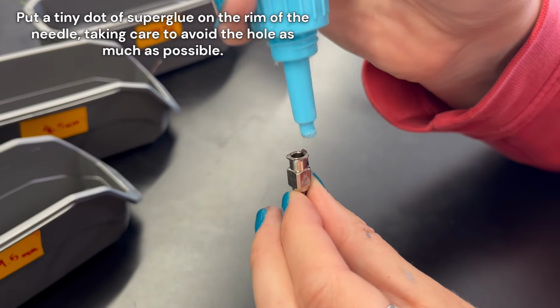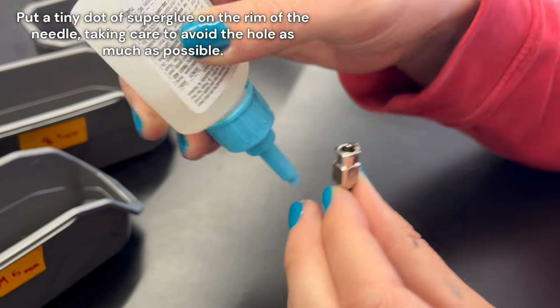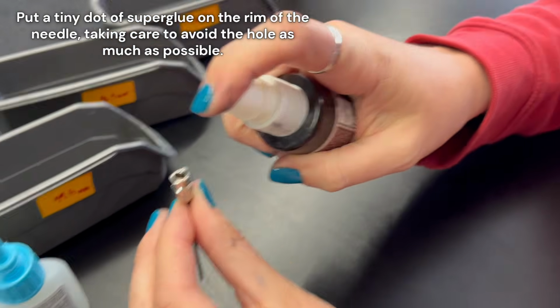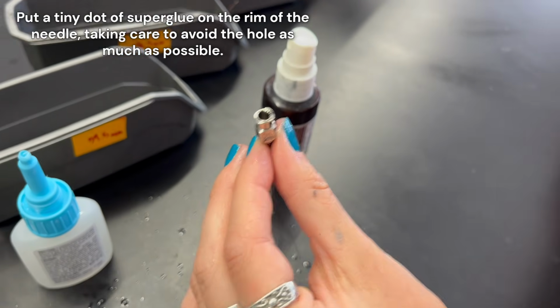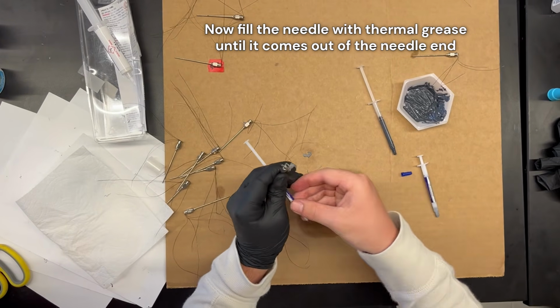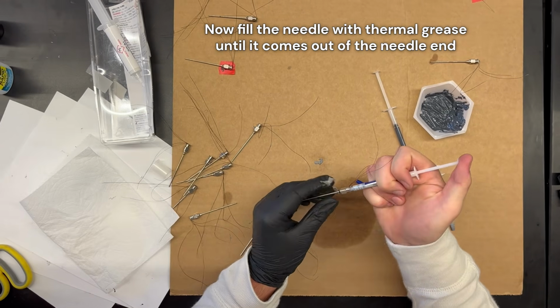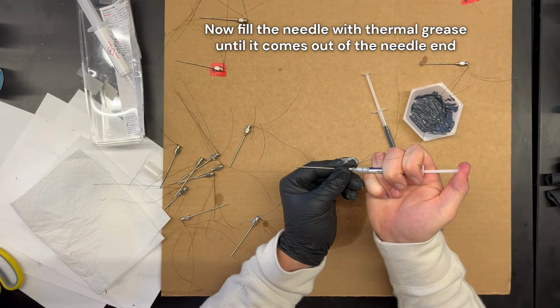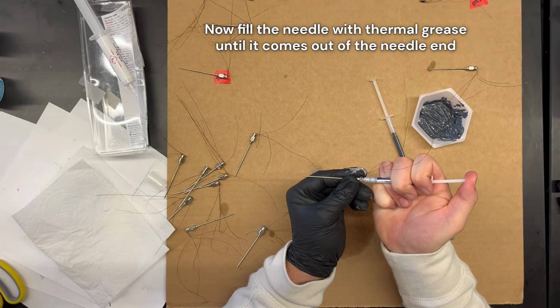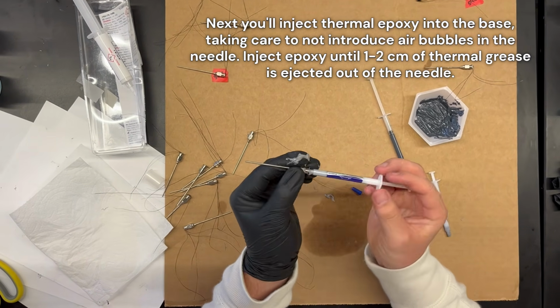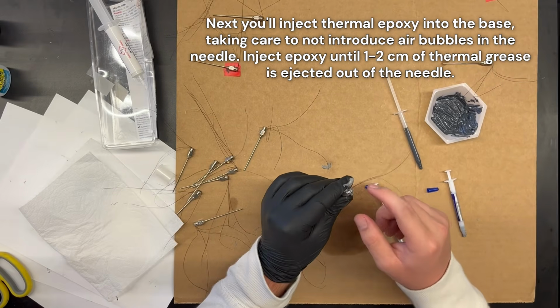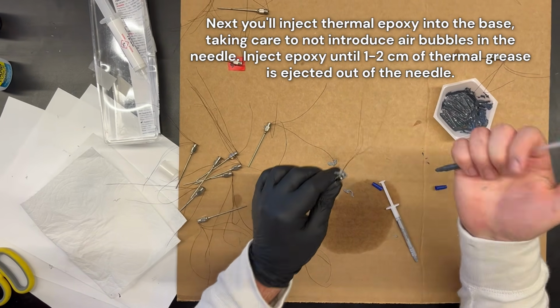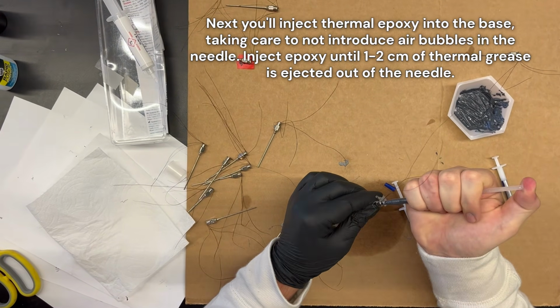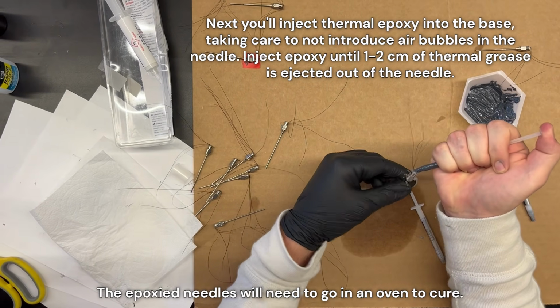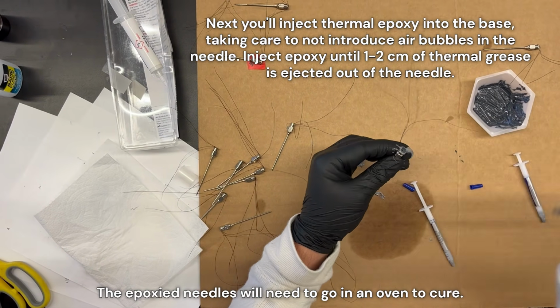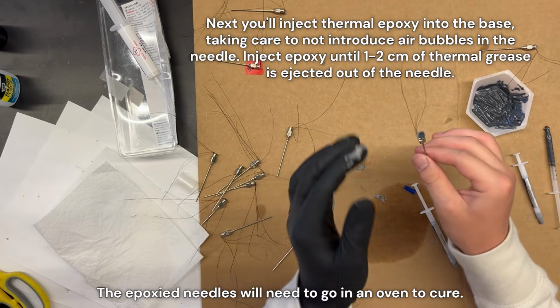Use a drop of superglue to hold them in place, and if you have it, you can use accelerant to cure the superglue instantly. You can either fill the needle completely with thermal epoxy, or use thermal grease to make it easier, as we do here. Fill the needle with grease until it comes out of the end, and then mix a batch of the thermal epoxy and fill a syringe. You want to inject enough thermal epoxy to hold the thermistors and grease in place. I like to push out 1 to 2 centimeters of grease, but try not to push any air bubbles in.